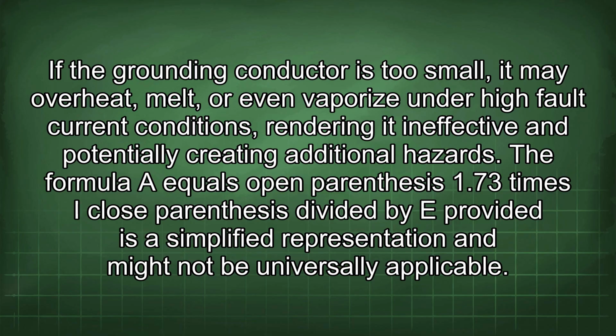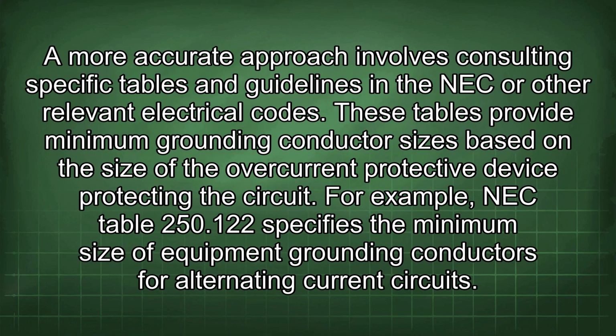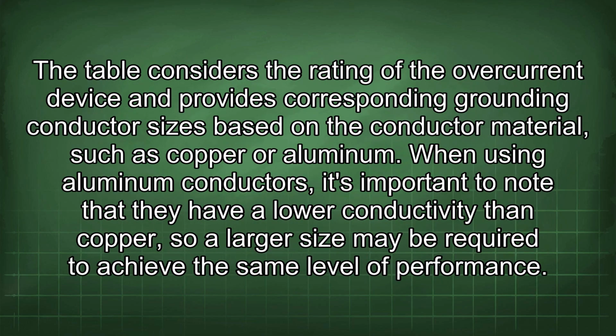The formula A equals (1.73 × I) / E provided is a simplified representation and might not be universally applicable. A more accurate approach involves consulting specific tables and guidelines in the NEC or other relevant electrical codes. These tables provide minimum grounding conductor sizes based on the size of the overcurrent protective device protecting the circuit. For example, NEC Table 250.122 specifies the minimum size of equipment grounding conductors for alternating current circuits. The table considers the rating of the overcurrent device and provides corresponding grounding conductor sizes based on the conductor material, such as copper or aluminum.